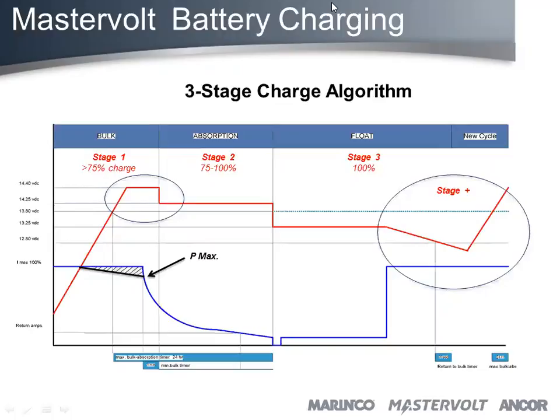When you float, it basically maintains the voltage at 13.25, and any current required for loads connected to it will come out of the battery charger and not out of the batteries.